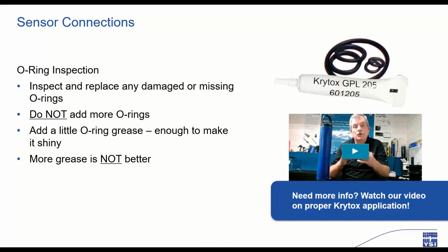I want to mention the little O-rings at the base of the ProDSS and EXO sensor, the little ones just above the threads on the mounting nut. These O-rings are there only to help keep debris out of the base of the sensor. They don't have any impact on keeping moisture out of the connection. When these little guys look stretched out, remove and replace them to keep them from getting down into the threads of the sensor. YSI recommends Krytox grease because it's the very best. If you don't have that, silicone grease can be used.